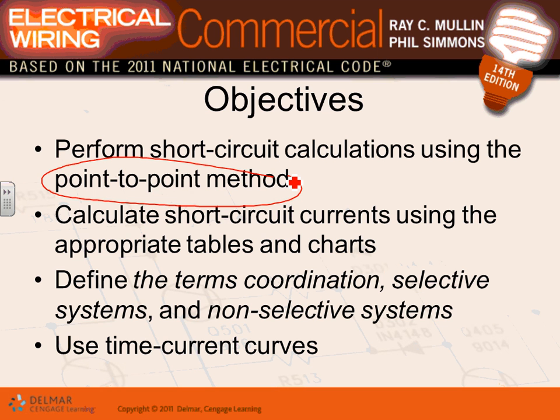Short circuit using tables and charts. If you don't have a software like SKM, that's how they do it. They use charts, but almost every engineering firm has a software, typically SKM, and they do all the calculation with it. And again, you guys will be introduced to it next week.